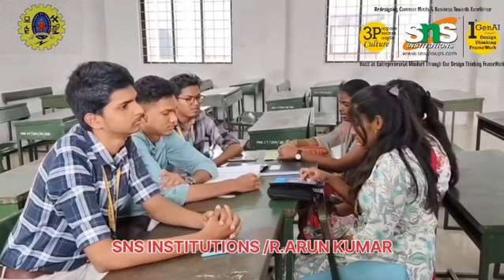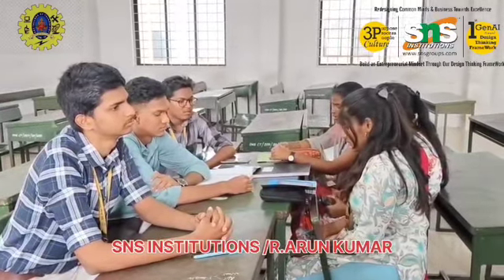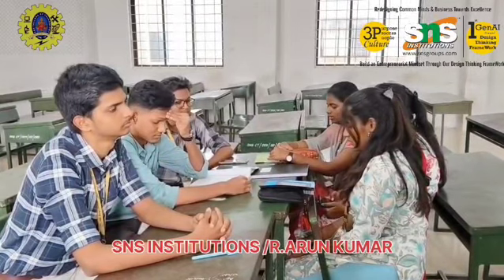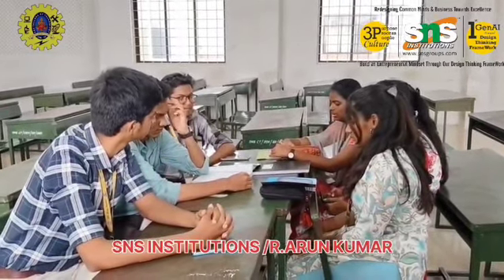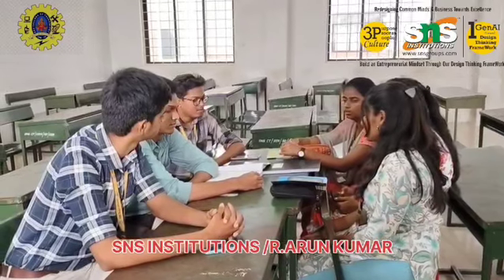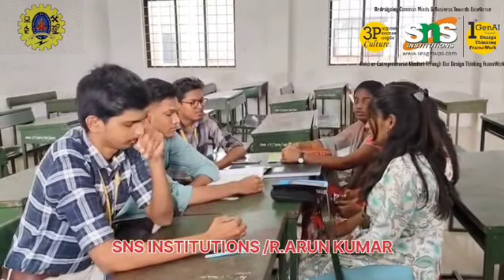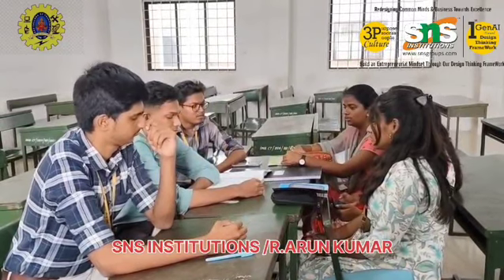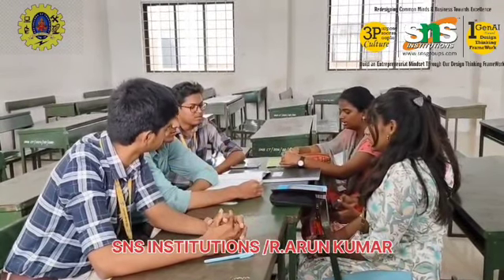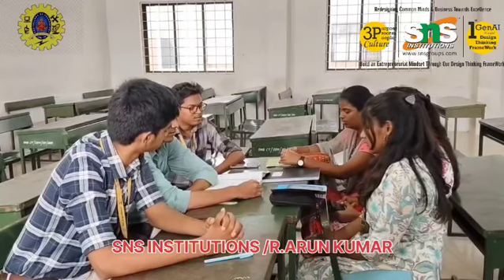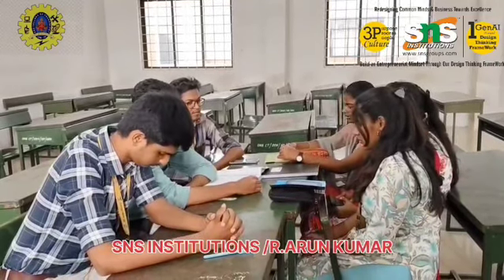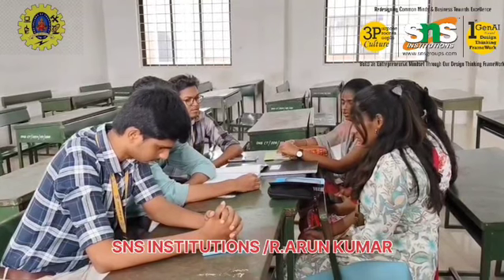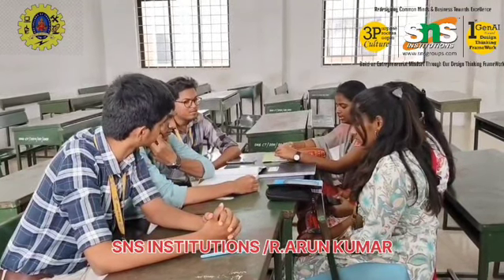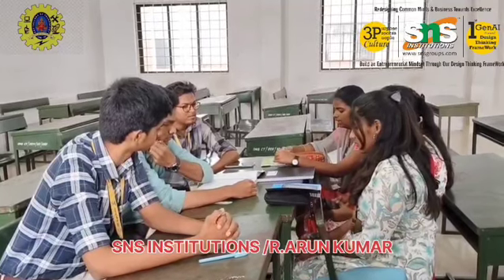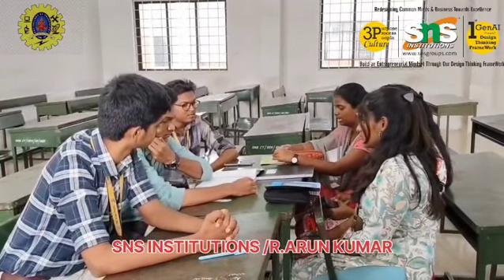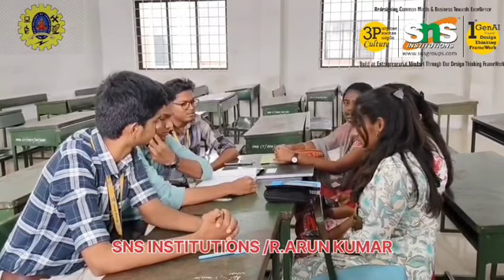The next topic is readability. Readability is defined as the closeness with which the scale of an analog instrument can be read. Resolution is the smallest change in the measured variable to which an instrument will respond. Dead zone is the largest range of values of the measured variable to which the instrument does not respond, with the delay in response called dead time. Backlash is the lost motion or free play of mechanical elements such as gears and linkages.